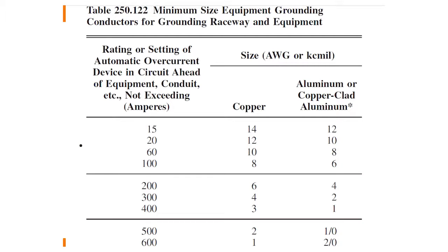And so we're using a much smaller equipment grounding conductor because the only thing that equipment grounding conductor is being called upon to do is to carry current back to the overcurrent device to trip the overcurrent device. And so these calculations are based on fault current calculations and undersizing or downsizing those based upon the allowable fault current that would typically flow in these types of circuits and the minimum size conductor that would not fuse and come apart while the overcurrent device is trying to do its job. So that's where all that kind of comes from.